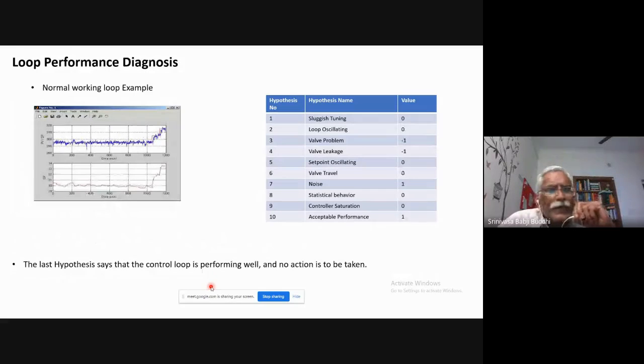Next we have a loop which is operating normally. It doesn't have any issues. As you can see here, it is controlling well, and there is a control output signal also. There are no major undesirable trends or anything. If you look at the results of the hypotheses, all of them are false, and only noise is there. Noise, again, if it is not very high, we can ignore that. Then we say that it is showing acceptable performance. So we can conclude that for this set of data, the control loop is performing properly. Okay.